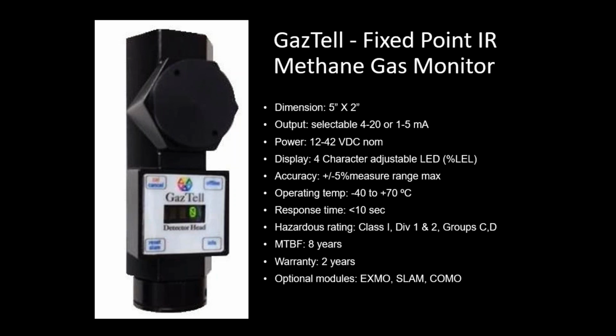Also remember, these are fixed in space point detectors, which basically means that wherever the detector is, it's only as good as if the gas gets to that point. If I had two detectors 2 feet apart from each other, one detector theoretically could go off while the other one didn't because the gas was higher concentration at one of those detectors rather than the other. So they're point in space monitors, and you should be aware of that when you buy them, when you figure out how many you need and where you place them in a particular room or application.